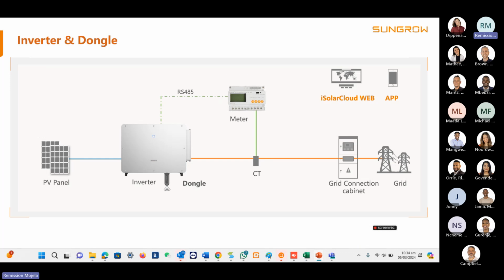And then we have applications of our systems. So basically the first application is inverter and dongle, meaning if it's the CX version, it is the inverter and the IM4. And then if it's the inverter and IM4, you just need the meter, the CT, to be able to do zero export, or you can still feed back to the grid depending on the settings, but you just need the inverter and the meter, and that will be the basic setup.